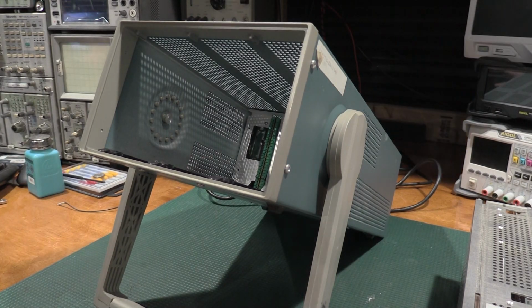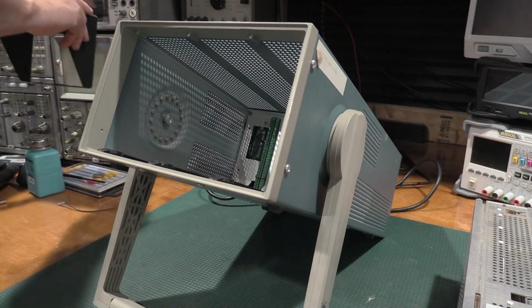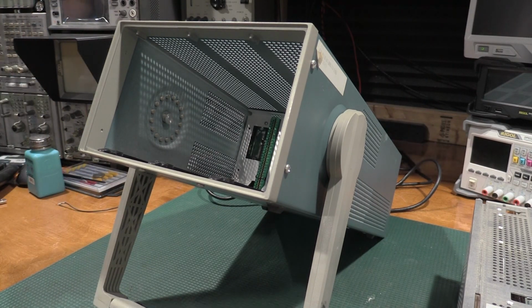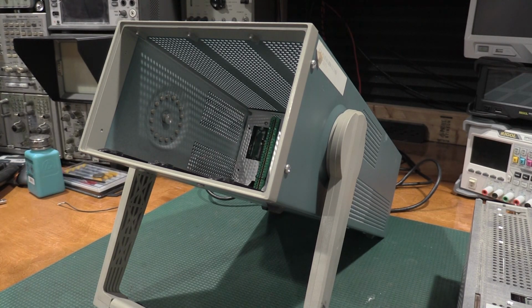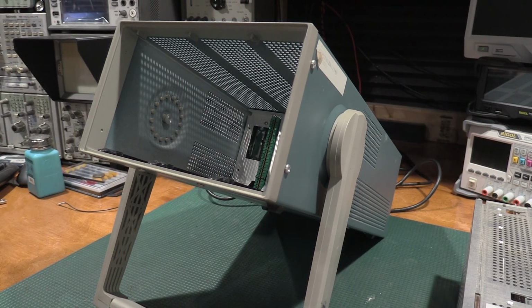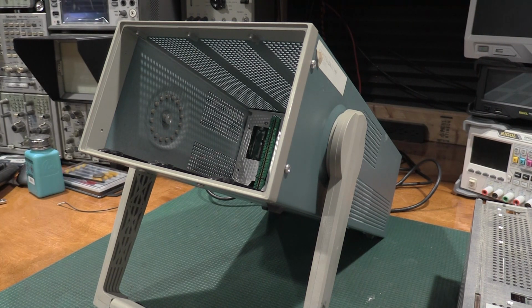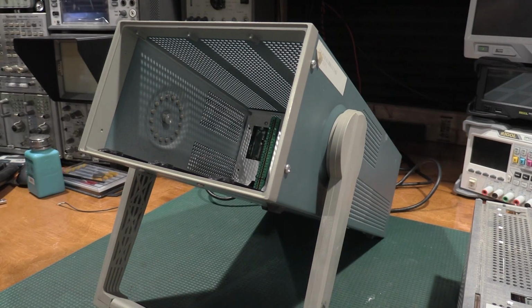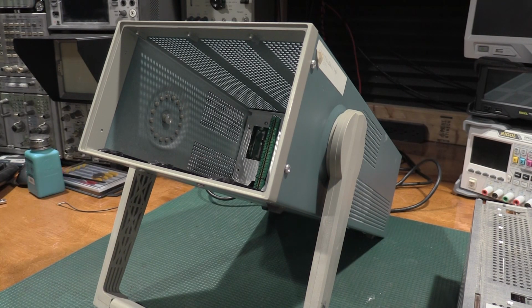Okay, we have the power frame on, and our goal here is no smoke. Right now there's 0 volts coming in from the isolated supply, and I have the current limit set to 1 amp, but we don't have any plugins, so that's fine. There's 60 volts, we're drawing about 800 milliwatts. Bulbs are not lighting up at all, so we're getting good indications there. There's 101, just over 2 watts, so we'll go up to 120.